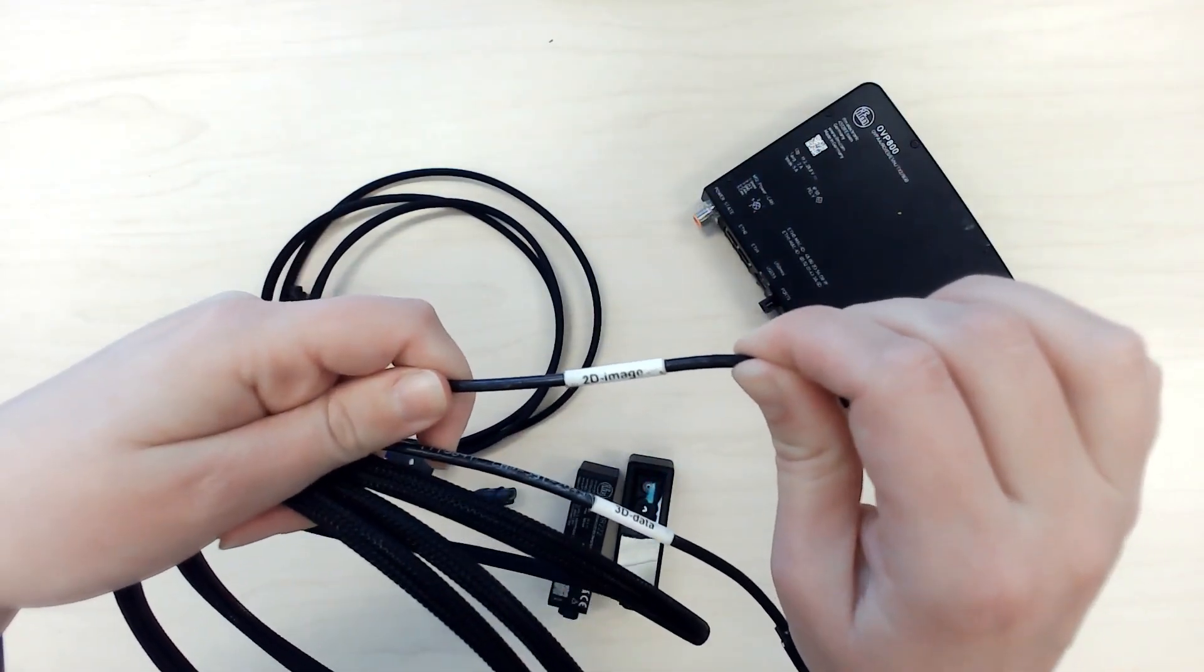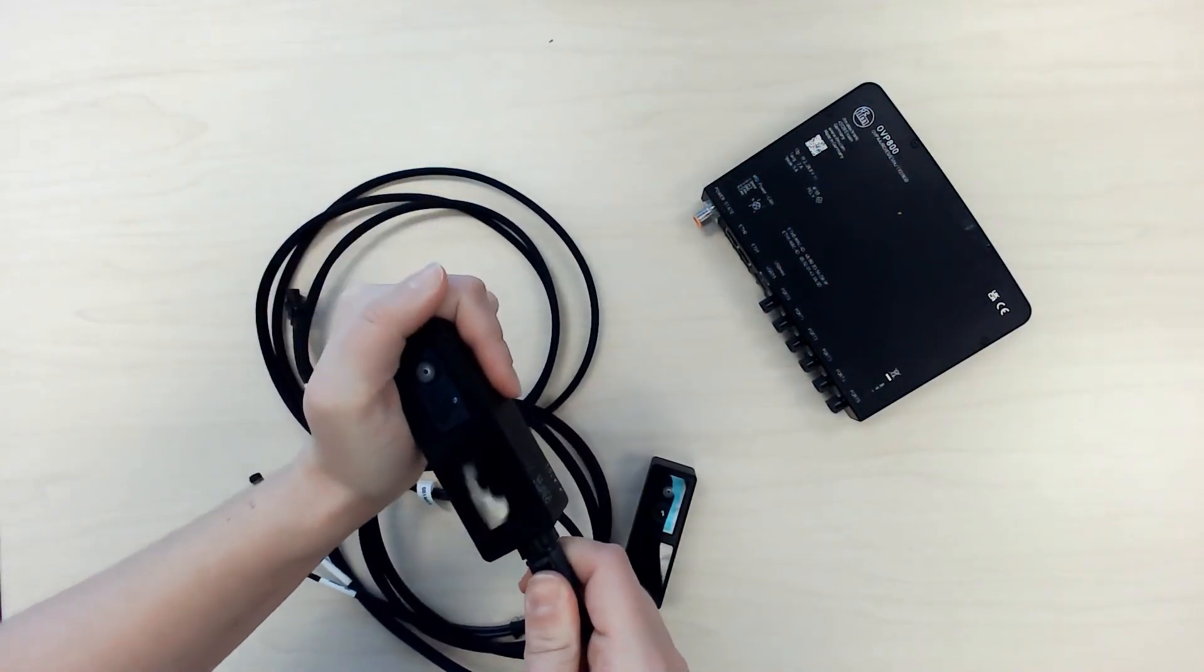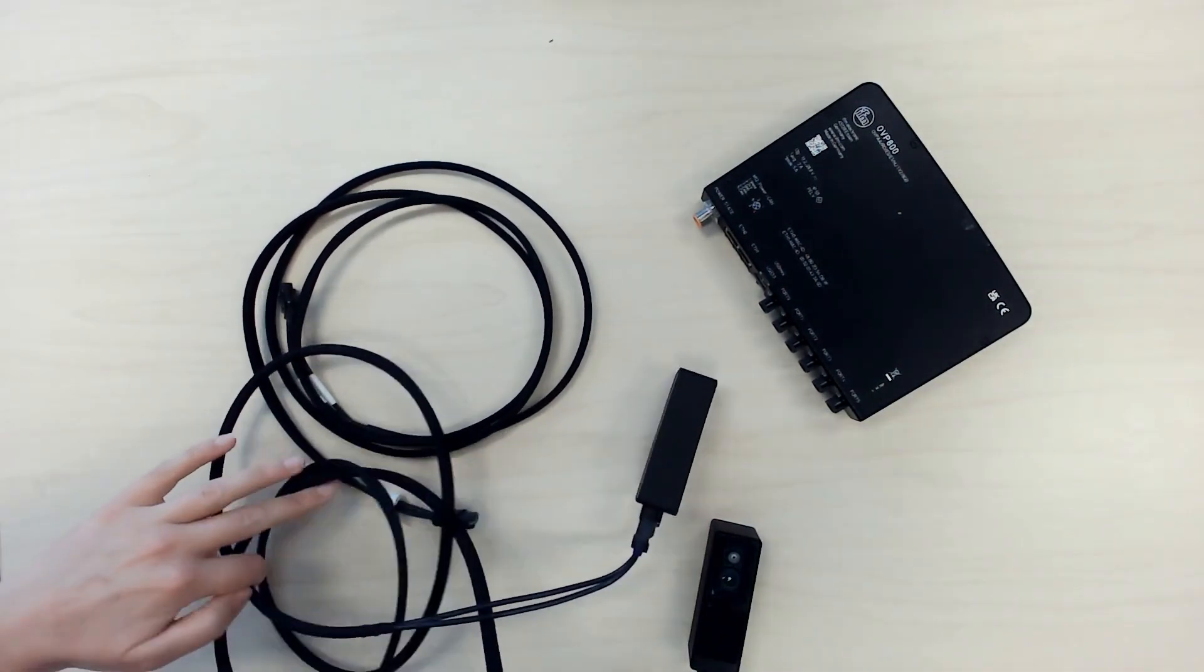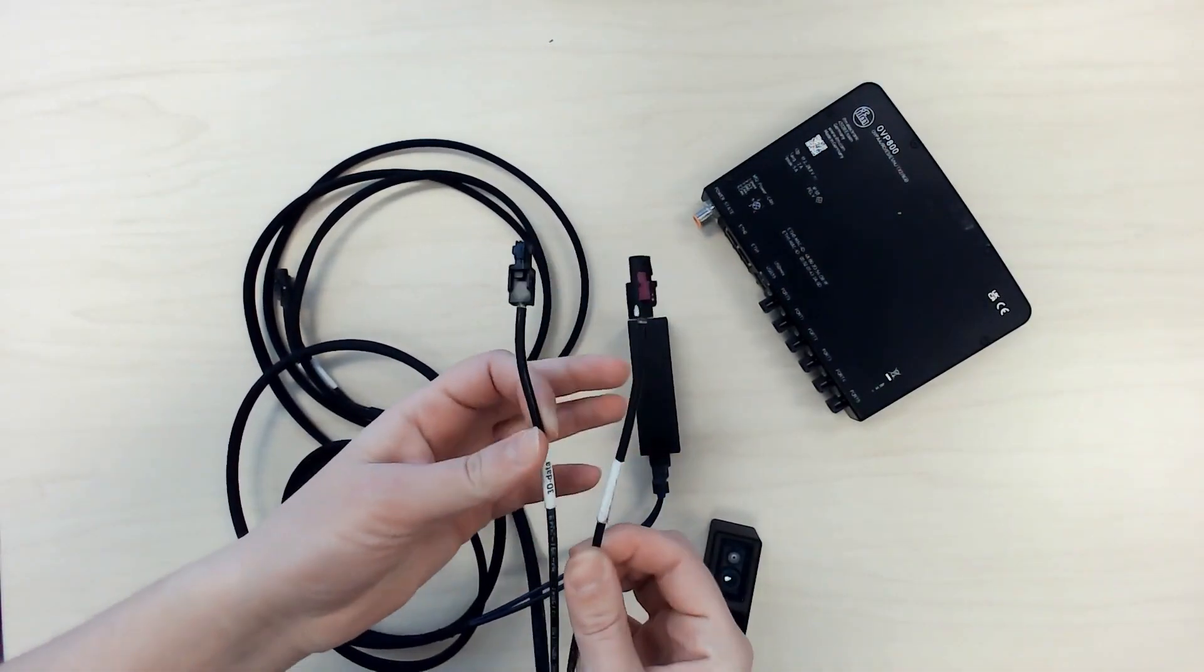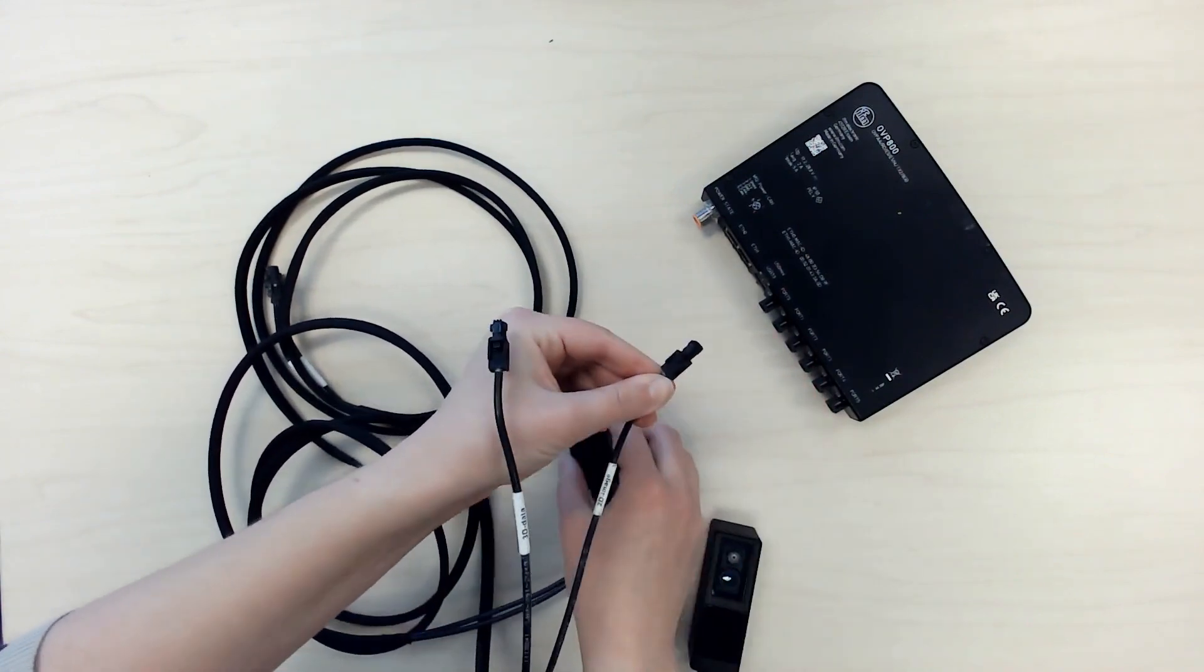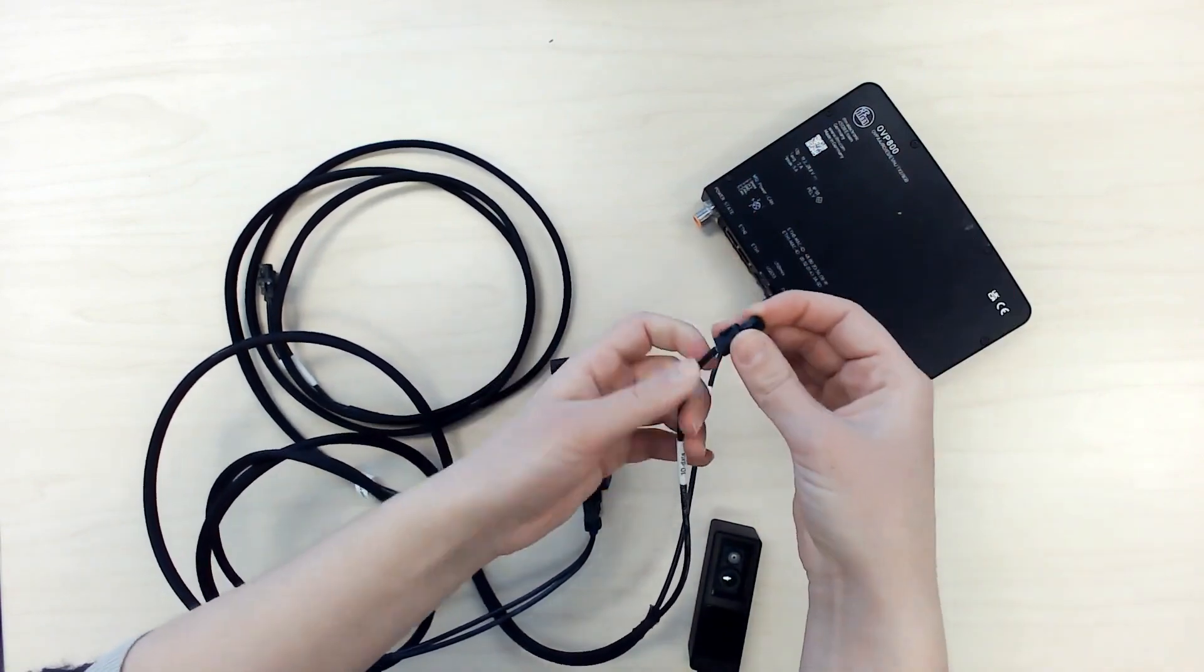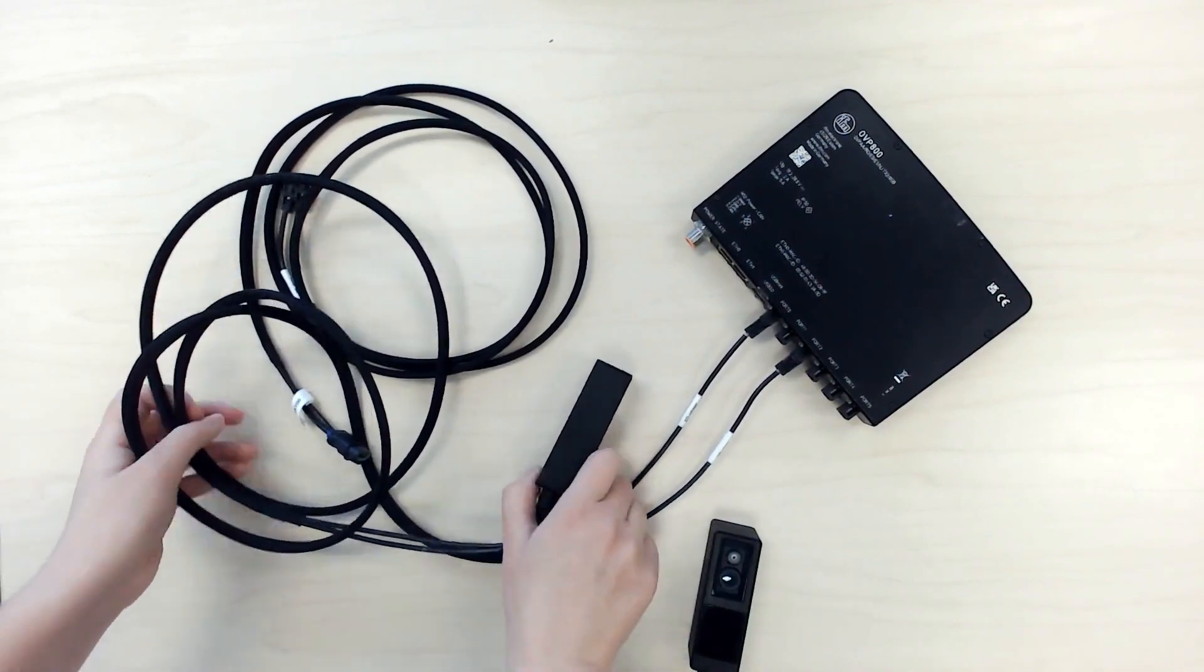Now you'll take the end with the single connector and connect it to your camera head. And then you'll take the two connectors and connect them to the VPU. And this is where you need to be careful. You need to make sure that the two connectors are not connected next to each other. So what I'm going to do here is connect my 2D onto port 0, and connect the 3D onto port 2. This is very important to remember. You cannot have the 2D and 3D connected next to each other.